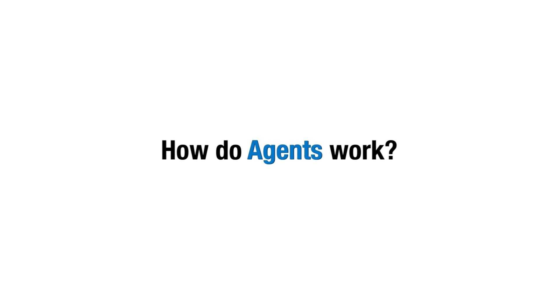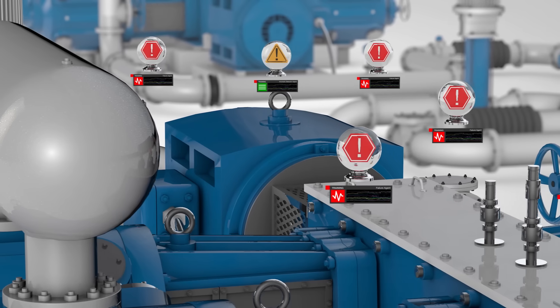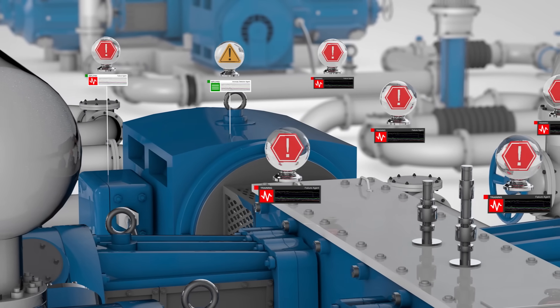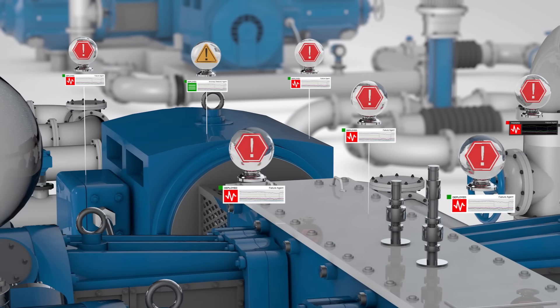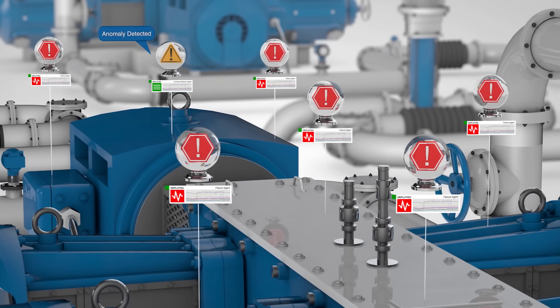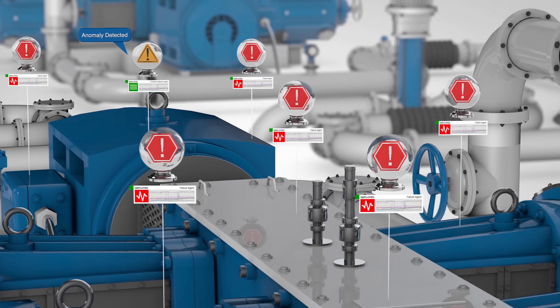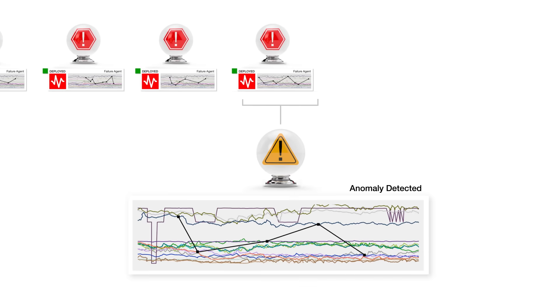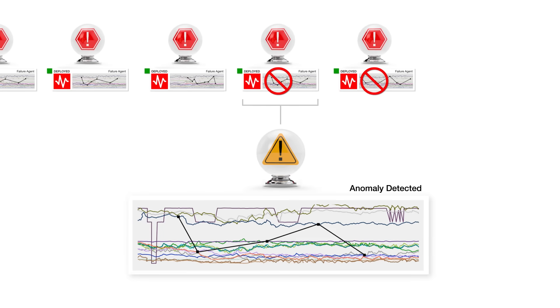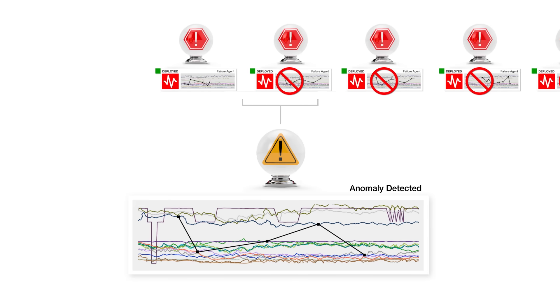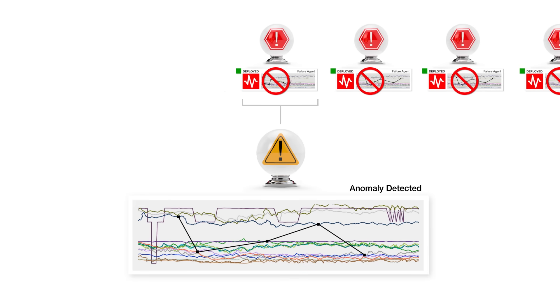How do agents work? Once agents have been trained from historical data, they are deployed to monitor live equipment feeds. All deviations from normal behavior are labeled as anomalies and detected by the anomaly detector agent. If an anomaly does not match the signature of a deployed failure agent, the anomaly triggers an alert requesting an inspection to determine the cause.